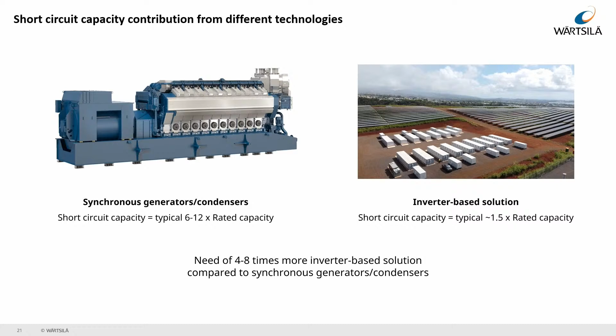You have power electronics, and these cannot be overloaded. They have a built-in protection of normally 1.5 times rated capacity, which means it will limit the output from these inverter-based solutions to 1.5, just to protect themselves. So we definitely see that synchronous generators and condensers are superior to inverter-based solutions when it comes to providing short circuit capacity.